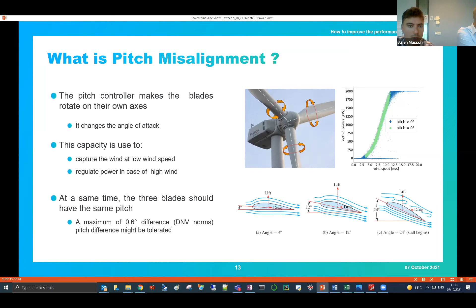So most of the time, normally the 3 blades should have the same pitch angle at the same time for most of the turbine. And there is a tolerated difference according to DNV here between 2 blades of 0.6 degrees. But it happens that the difference is higher, and so you have a pitch misalignment. So that's what we call a pitch misalignment. For example, 1 blade has 1 degree more than the 2 other blades. That would be a misalignment. It is not seen by the controller, and the controller has the same 2 values, but in reality there is a pitch misalignment. So it's quite frequent.